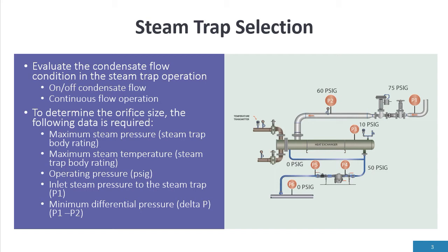The body rating has to be rated for 150 psi at 366 degrees because we're underneath the code, the power piping code or depending on what country, there are codes that govern steam and condensate piping. The operating pressure, an example would be 75 psi.